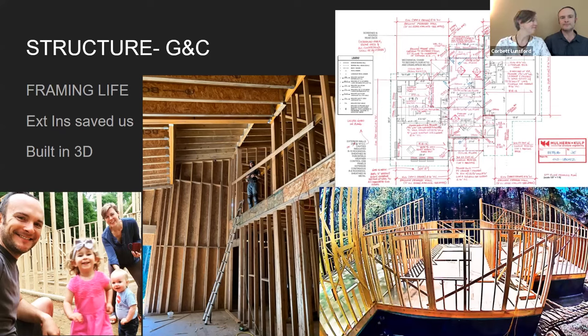Have compassion for builders — whether they're building in a factory or on site. Some of the things taught in building science were obviously thought up by people who don't actually build houses. Also, if everybody talks about stacking your studs between floors and you don't do that, you can't bring ducts up between floor joists — which Corbett didn't know until he was trying to install ductwork. They had to install soffits to reframe some areas to accommodate it.